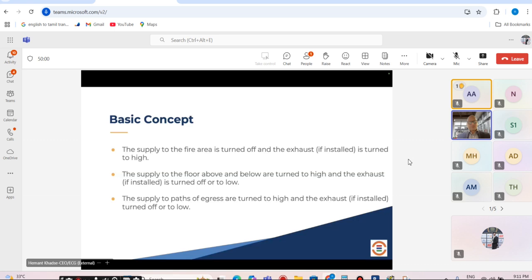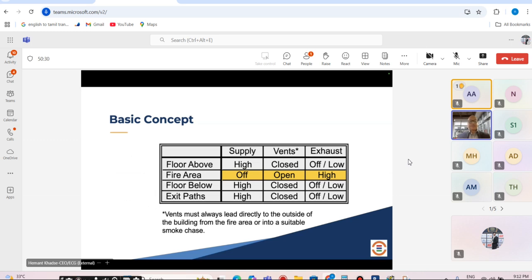Now, when you do that pressurization technique, the codes also give various options. Again, it is an engineer's responsibility to design it effectively: how my fire zone is getting activated, and if that fire zone is activated with an exhaust, then how my adjoining floors are going to behave at the same time. Specifically, if you look at this particular slide, you will see that you can create logic like, if there is a fire floor which is going to create the exhaust on, the floors above and below can be pressurized so that the smoke doesn't transfer to the adjoining floors.